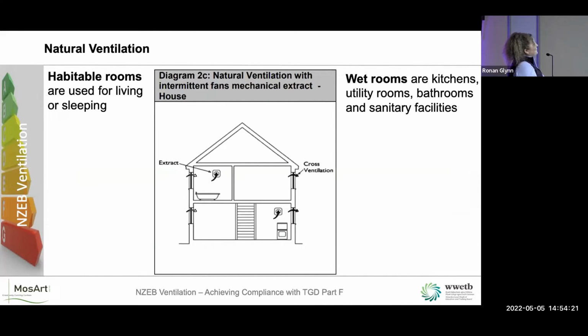So Manuel talked a little bit about calculating mechanical ventilation. So did Gary. So I'm just going to focus on natural ventilation, just not to be repeating it. Part F is very particular about what is a wet room, is a kitchen, a utility, a bathroom or a sanitary room. Habitable rooms then are other rooms, and there's other little rules and regulations about that as well. So what we have is our background ventilators.